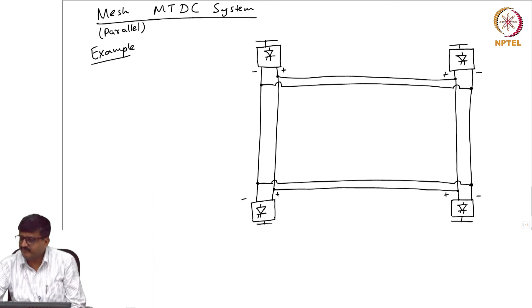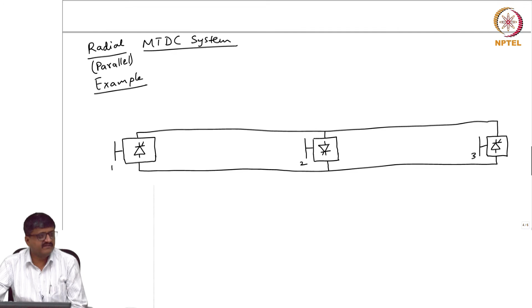So, here I have an example of what is called a mesh MTDC system, 4 AC buses, 4 converters, at least one of them operating as rectifier, at least one of them operating as inverter. Now, it should be obvious why it is called parallel. We are connecting all the DC side terminals in parallel. If you take all the 4 converters, the DC side terminals are connected in parallel. But why is it called mesh? By looking at the example of this mesh and the example of this radial, what is the difference? Do you see any difference?